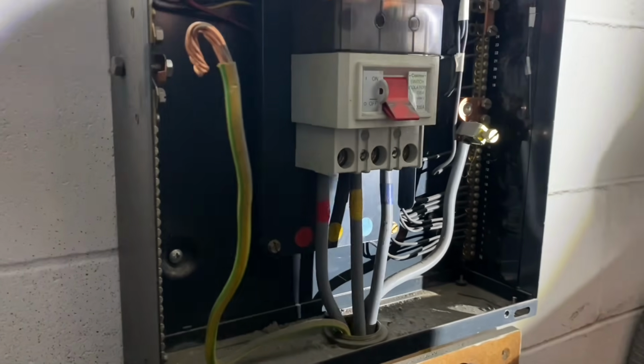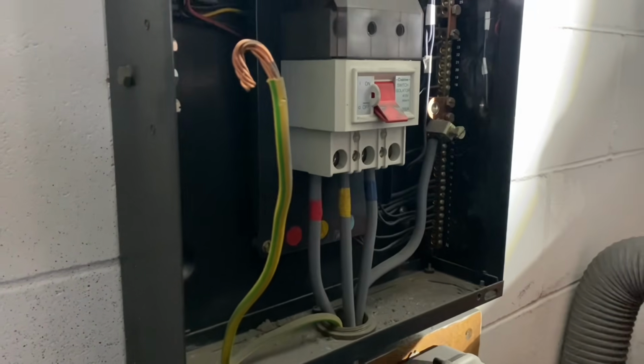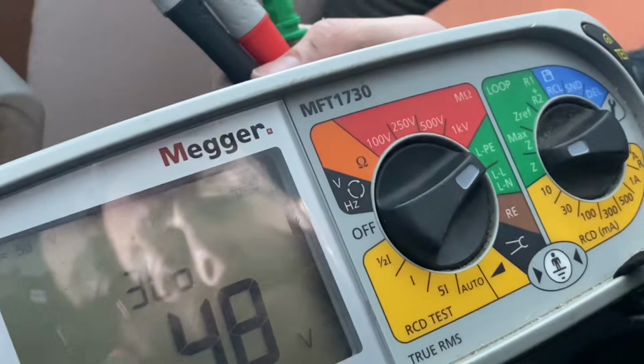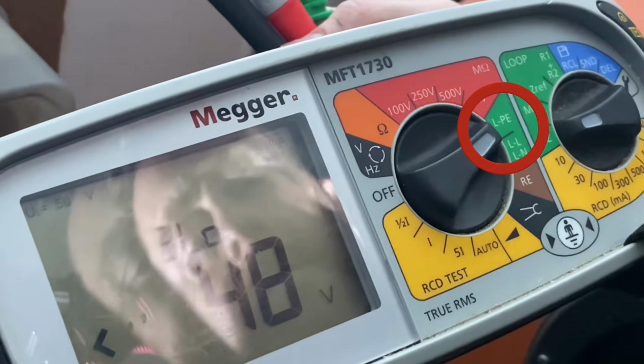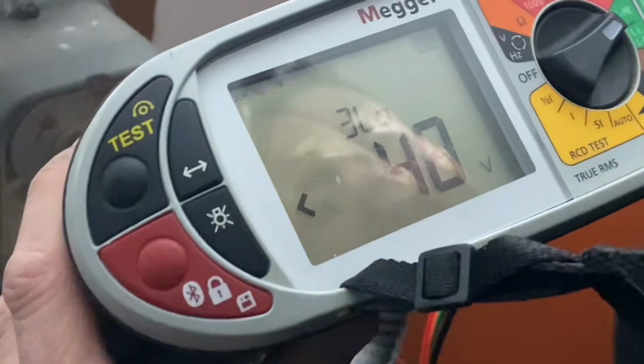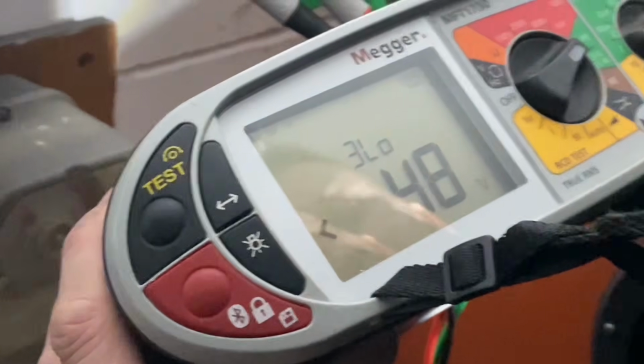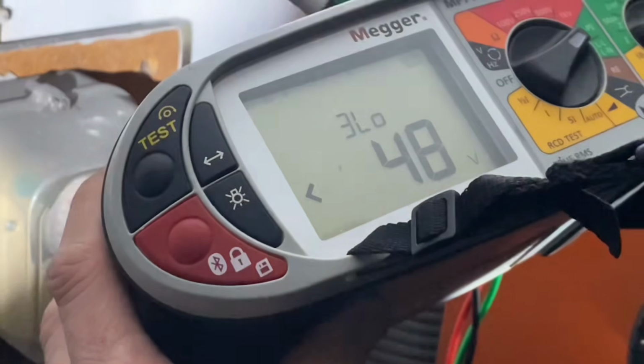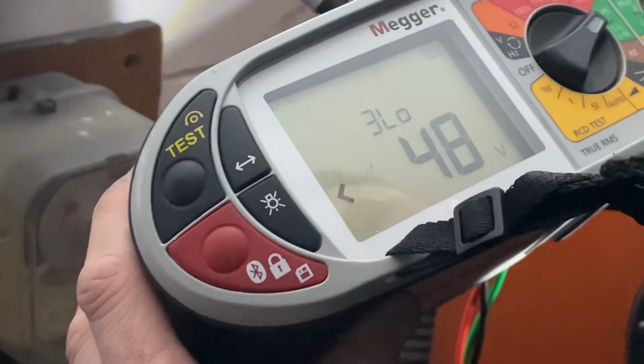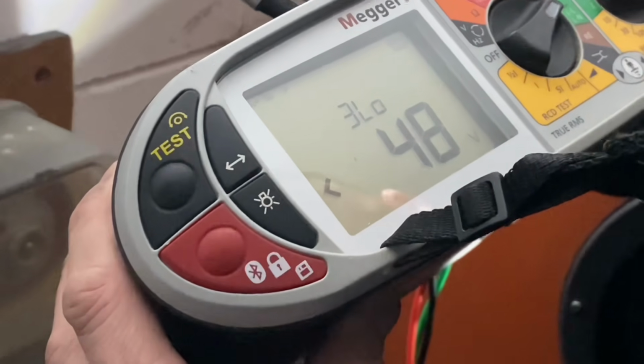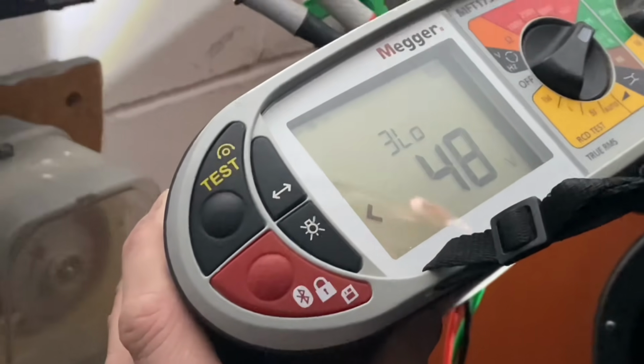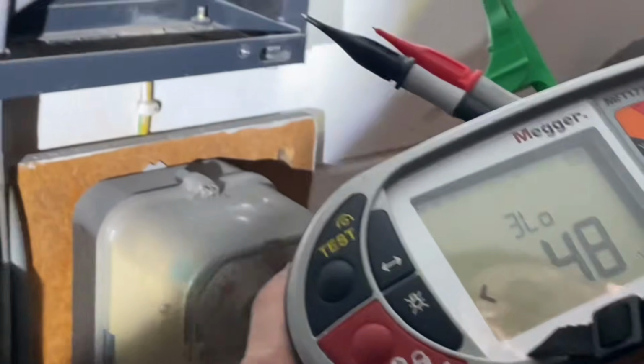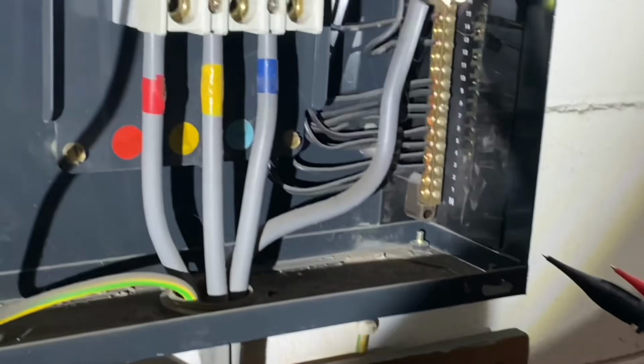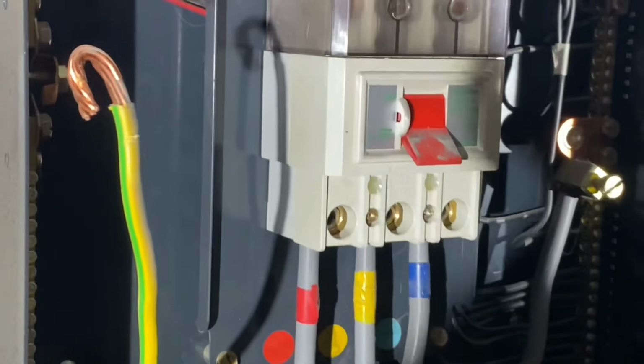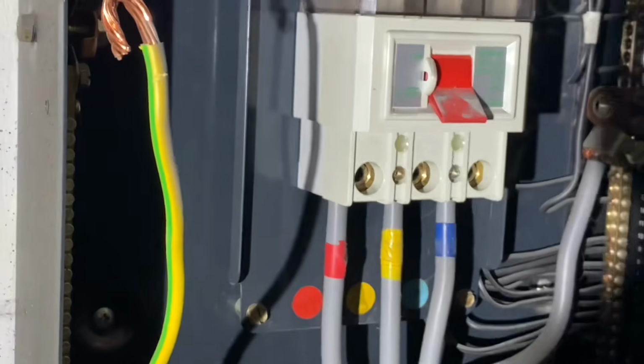And we're going to set up our instrument now in order to carry out that external earth fault loop impedance test. So we've set our Megger MFT1730 up to L-PE, and you're going to do it on the 3-lead low setting. We could have done it on high because there are no RCDs, but you think this will probably be the standard practice to get used to, Matt, is that right? When we've got so many RCDs around, we go for the low setting. Yes, yeah.